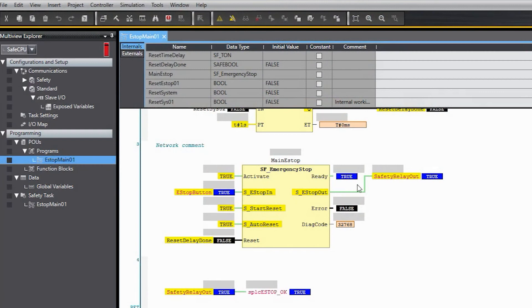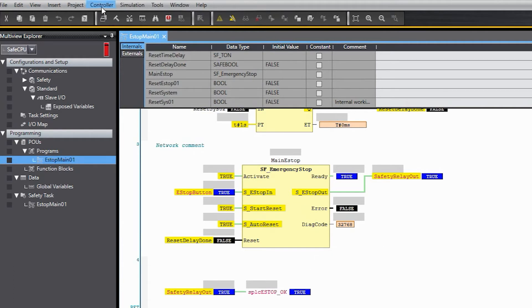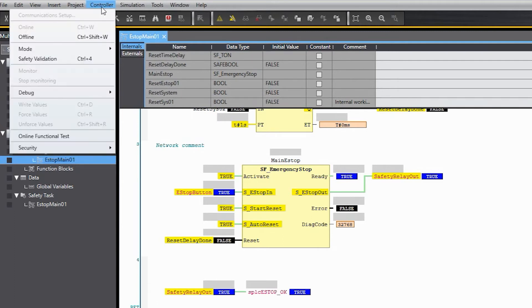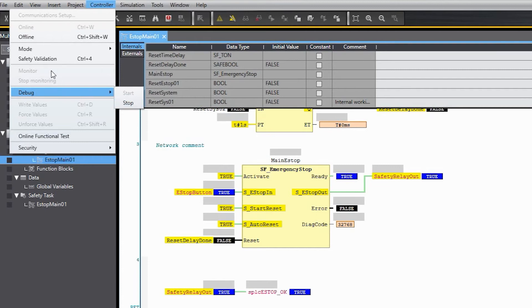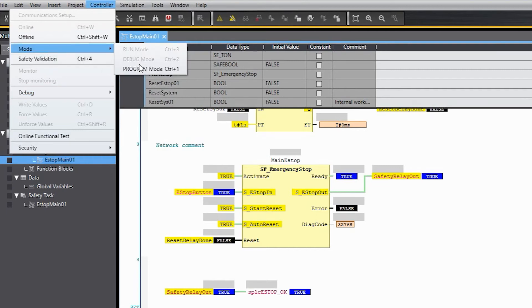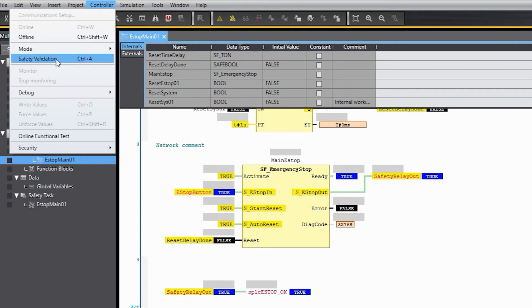So now we can test this and make sure everything's working but let's assume we've already done that and we're ready to deploy this program. Maybe this is a program that we deploy on every machine. So we're just ready to make it go and work so that the safety PLC will run this on its first cycle or whenever it powers up. So we have to go down here and we can go to debug but there's only stop so we don't want to stop it. We can go to mode and there's only program. We don't want to go to program mode so that leaves safety validation and what we'll do is validate the program.